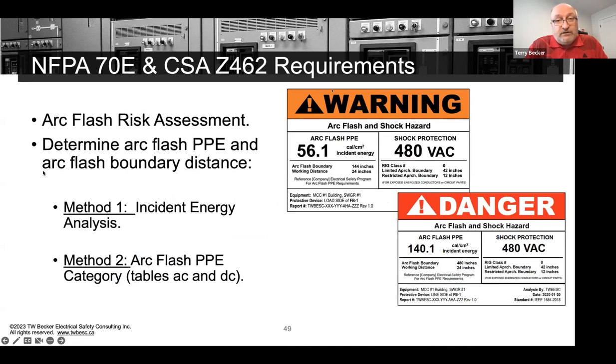All right, with respect to the arc flash PPE, there's two methods to determine the PPE and the arc flash boundary identified in 70E and Z462: incident energy analysis by a P.Eng or P.E. electrical engineer with a report provided to the equipment owner and install equipment labels. These are compliant equipment labels that you see on the screen, which I could explain in more detail if you are interested, but they're compliant labels. And the problem is from these studies, there's lots of non-compliant labels out there that aren't helping the worker. They're confusing the worker. So incident energy and labels, or the arc flash PPE category method, or what's quoted as the table method for AC electrical equipment and DC electrical equipment, meant to be far simpler to use if we don't have incident energy analysis studies.